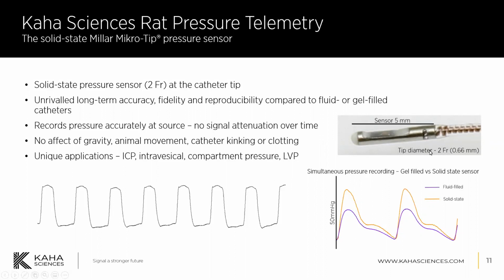There's no need for a pressure signal to move through the fluid or gel of the catheter into the transducer, which is located in the telemeter body. So this means that there's little signal attenuation over time. There are also no effects of gravity, animal movement, catheter kinking, or clotting that you might see with a fluid or gel-filled catheter. As well as arterial blood pressure, you can use this system for unique applications as well, including intracranial pressure, ICP, intravesical pressure, which is bladder pressure, compartment pressure, and left ventricular pressure as well. So with the incorporation of this solid state sensor, it's a really powerful system.